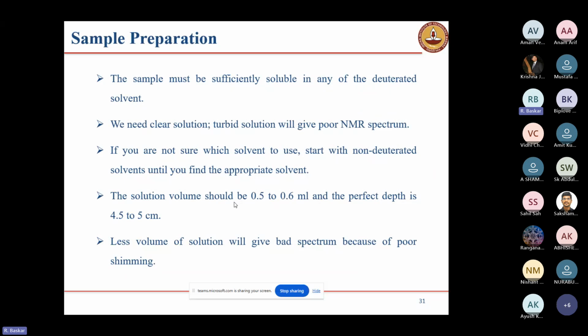For sample preparation, the sample must be sufficiently soluble in the deuterated solvents. Since deuterated solvents are very expensive, we should not check solubility in the deuterated solvent. First, you check solubility with the normal solvents, then you can use the deuterated solvents. The solution volume should be 0.5 to 0.6 ml, and the perfect depth is 4.5 to 5 centimeters. Less volume of solution will give a bad spectrum because of poor shimming.